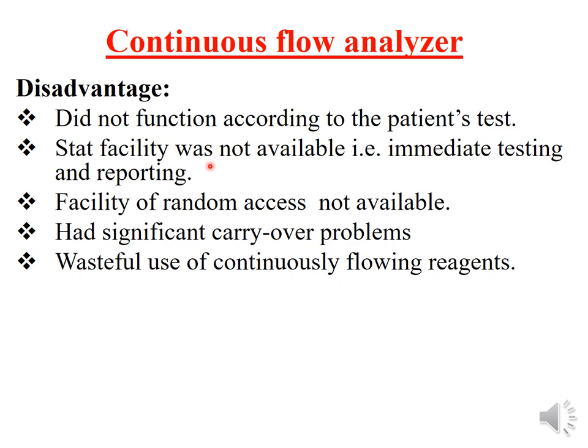Once you have started the procedure, if any sample needs to be done in an emergency you cannot change your priority. Once you have programmed it, that has to complete before the emergency sample can be run. This facility is known as the STAT facility.